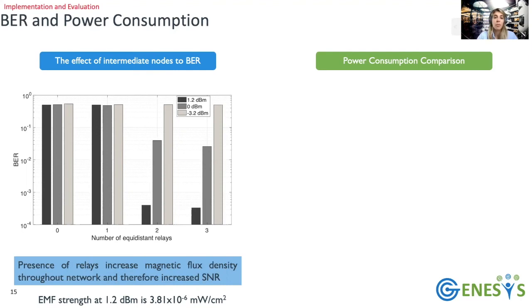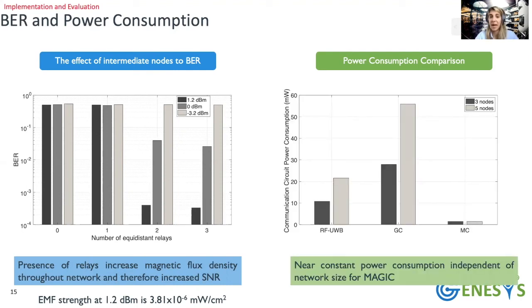Moving on, we compared the power consumption of MAGIC with similar intrabody networks using radio frequency in the ultra-wideband and galvanic coupling. The outcome of this comparison is that MAGIC has a lower power consumption than both methods, which is mainly due to its passive relays. Due to the fact that any additional node is a passive node, by expanding a 3-node network to a 5-node network, we do not see an increase in power consumption as we see in other competing methods.